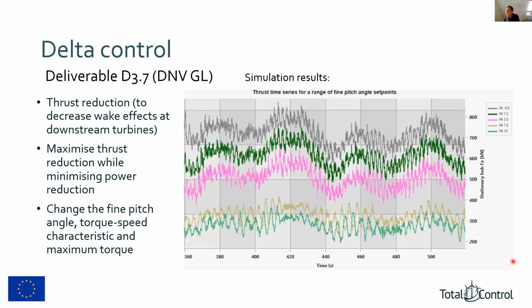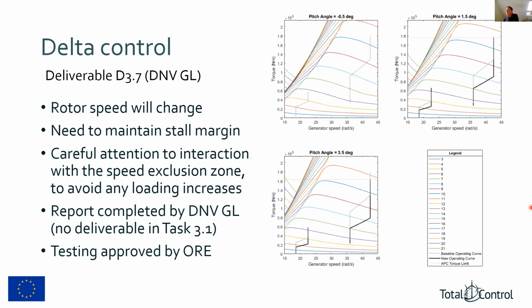The delta control - this is some example simulations showing the different thrust reductions, these are actually thrust time histories during the simulation. What we're doing here is trying to maximize the thrust reduction while minimizing the power loss by choosing appropriate pitch angles and rotor speed, torque-speed schedules to change the rotor speed. And this is implemented in the actual turbine controller. Again, this speed exclusion zone is an important factor here.